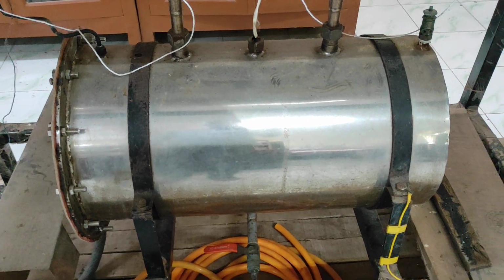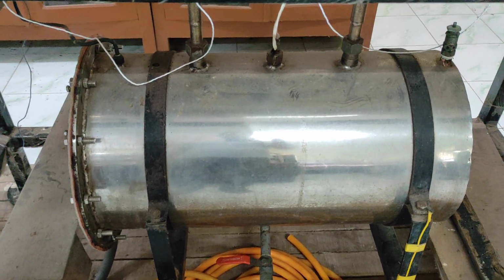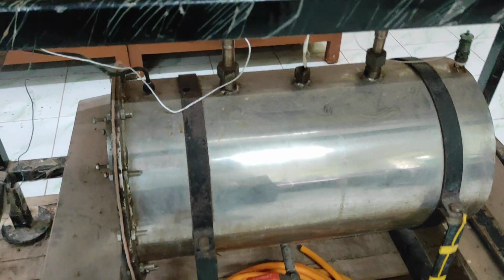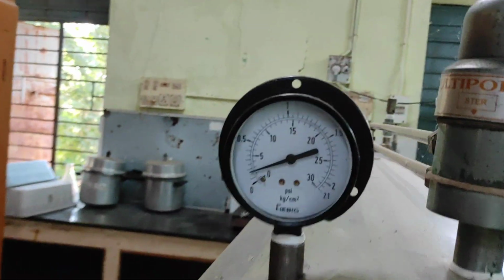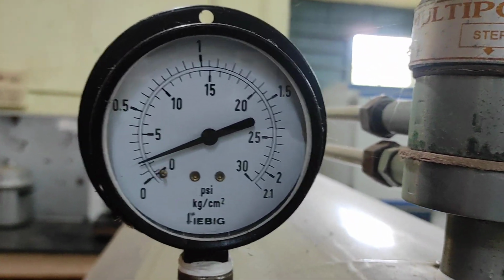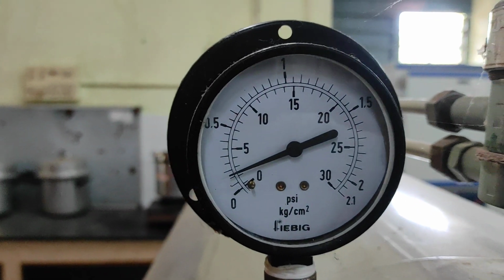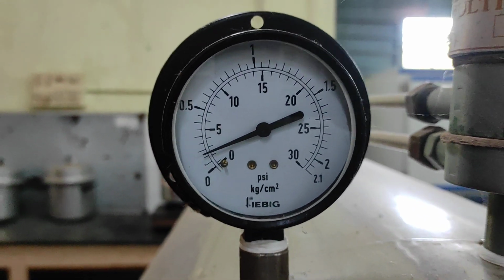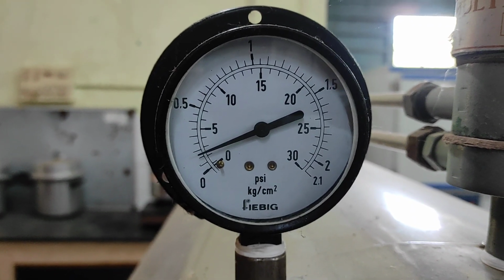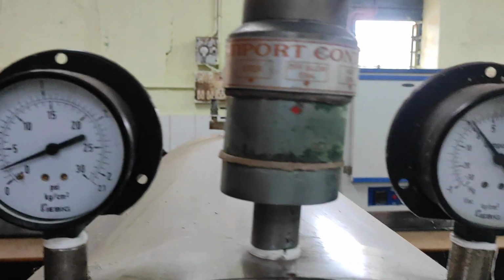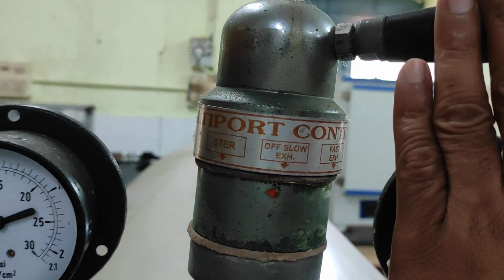So the heating rods boil the water, and the boiling water makes vapor, and the vapor goes to this chamber. That is the sterilization chamber. So hot water, then vapor formation. The vapor creates pressure, and this pressure can be measured and is visible here. Through this we can understand how much pressure is created inside the boiler. When sufficient pressure is there, generally 15 to 20, we release that pressure to the sterilization chamber like this.